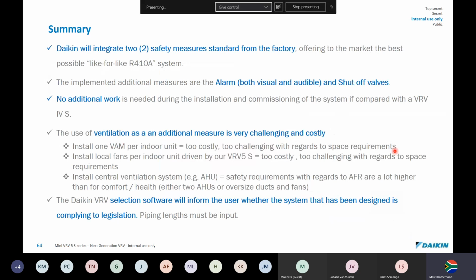So in summary, Daikin will integrate two safety measures which will come standard from the factory, offering to the market the best possible like-for-like R410 system. So you don't need to go and buy extra safety things. There's pump down valves and there's a leak detection system. The implemented additional safety measures are an alarm, obviously, so it's both visual and audible for the indoor, and the outdoor will have shut-off valves. No additional work is needed during installation and commissioning of the system when compared with the VRV4S.